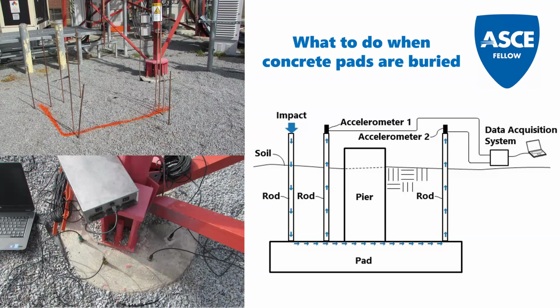But in reality, how thick do these pads normally have to be? I mean, it's just surface area pulling on the soil. I mean, what, a couple feet, 18 inches? How thick have we seen them before, Jim? I have seen a pad that was 4 feet thick. I didn't believe my numbers. I didn't believe my calculations. We dug it. We come off to the side here, dig a hole, and drive a rod under it. Sure enough, it's 4 feet thick. Only thing I can think of is somebody wanted to sell some concrete. And back then, it was only 350 a cubic yard to buy it and place it. And what is it, about $1,800 a cubic yard now?